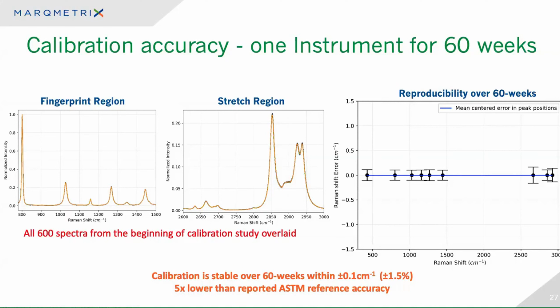Our Raman shift error in wave numbers ranges between negative 0.25 and positive 0.25 wave numbers. So that's about 5 times lower than the reported ASTM reference accuracy required. So we're quite proud of this, and this is all due to the solid state manufacture and quality of manufacturing that we build. We're ISO 9001 certified. We got that a year ago in May. And we're quite proud of the quality and the reproducibility of our instruments.